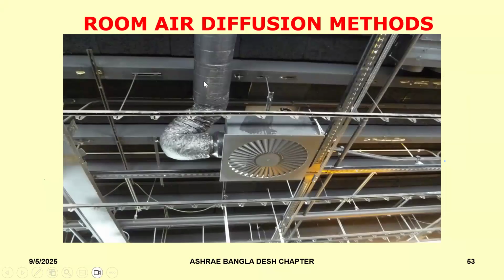I talked to you about how ducts need to be put properly. Now you see here, this is the kind of bend which has happened. Okay. I told you about having no ceiling and an outlet. So here is a swirl diffuser, no ceiling, good choice of an outlet, but its effectiveness is reduced simply because of the way we have connected the duct. So we need to make sure that even if we choose the right product, it's installed correctly. When I say installed, not just the diffuser itself, but also the connecting pieces to the plenum that you see over here.